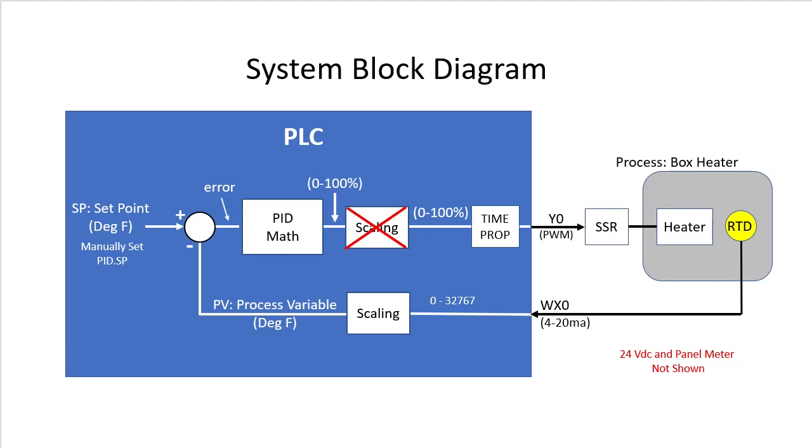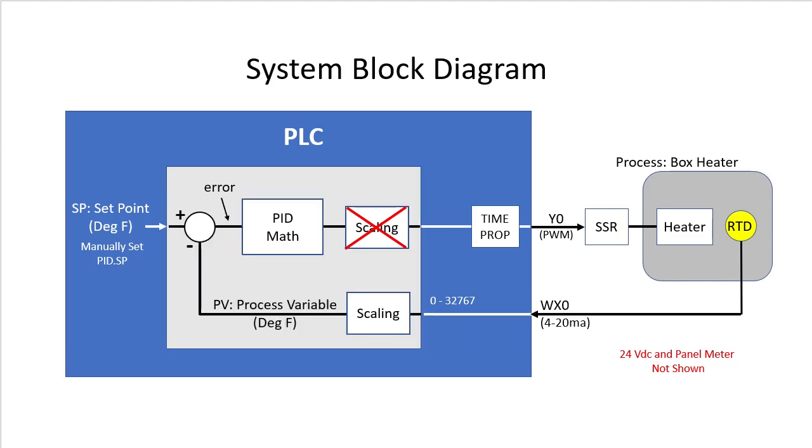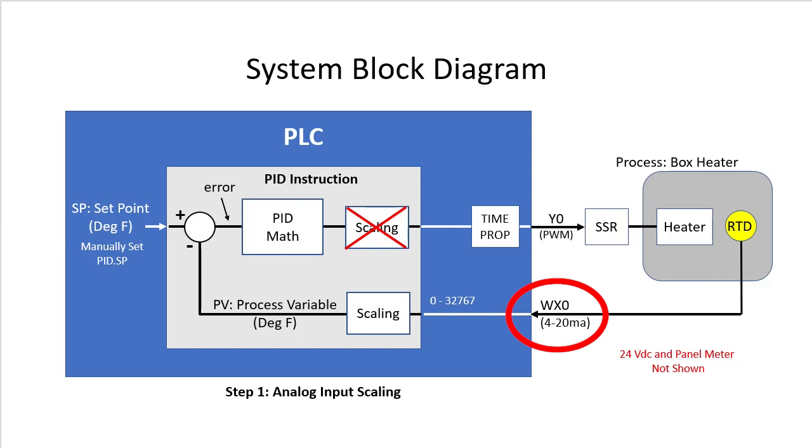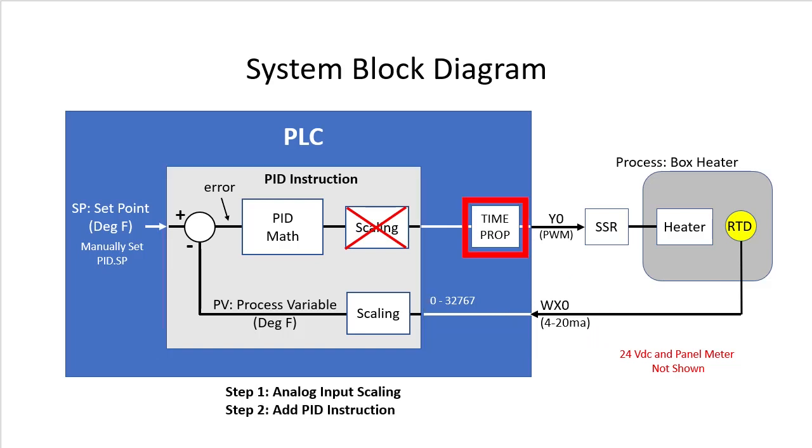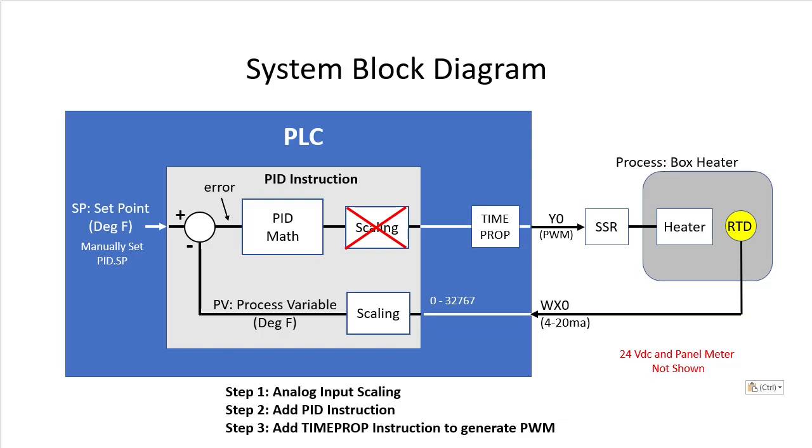Now this looks kind of scary, but guess what? All of this is done by a single instruction – the PID instruction. Once again, the Do-more engine does all the heavy lifting for us. So all we need to do is make sure the analog input is scaled correctly, add a PID instruction, and add a time prop instruction to generate the PWM output. Here we go.